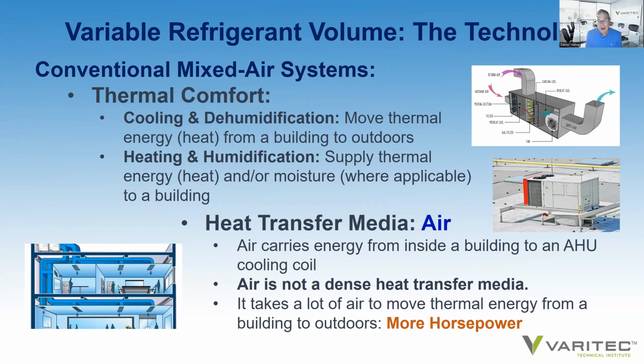and/or humidifying, which, by the way, the winter months are our driest times of year. In a conventional mixed air system, the heat transfer media, that is to say, what we use to move energy from the building to outdoors, is air. Air carries energy from inside a building to an air handling unit coil, where that air is conditioned, brought to a lower temperature. The energy in the air is stripped at the cooling coil and taken to either a condenser or a chill water loop, so that heat energy can be deposited outdoors.